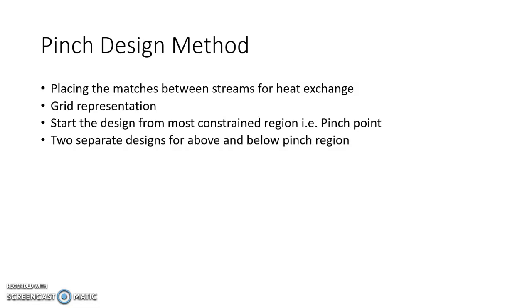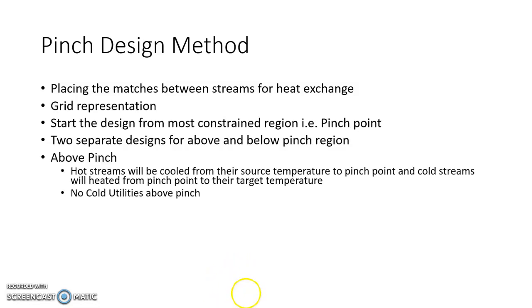In both regions — above pinch and below pinch — we start from the most constrained area, taking both hot and cold streams at the pinch and moving away from the pinch point toward the source temperature for hot streams and target temperature for cold streams. We'll understand this better when we look at the grid diagram. Two separate designs are made: one for above pinch and one for below pinch.